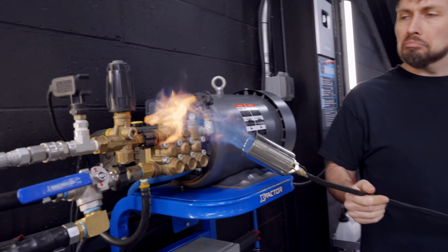They don't use the red wire on the one that comes off the pump. They use the red wire on the one that comes after the unloader valve at the outlet. Each pressure switch is the same, but it's where you land the wires on the switch.